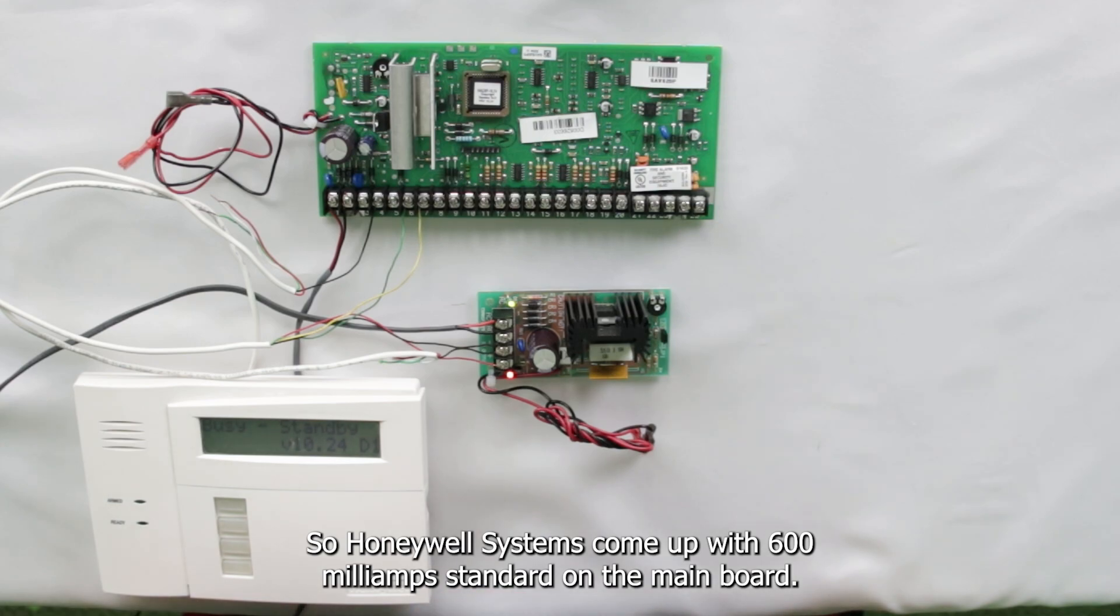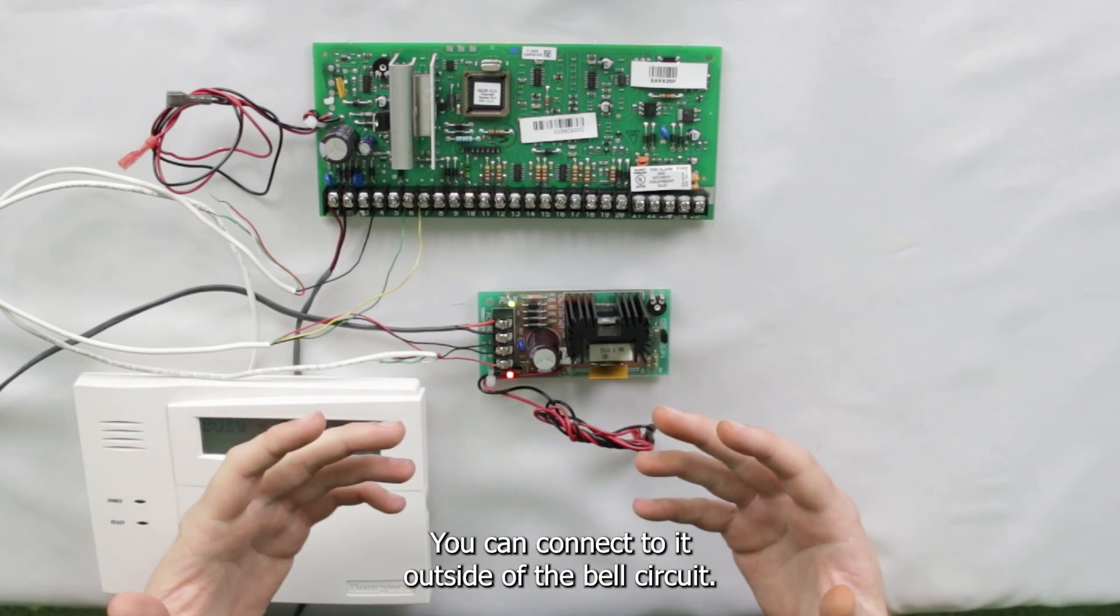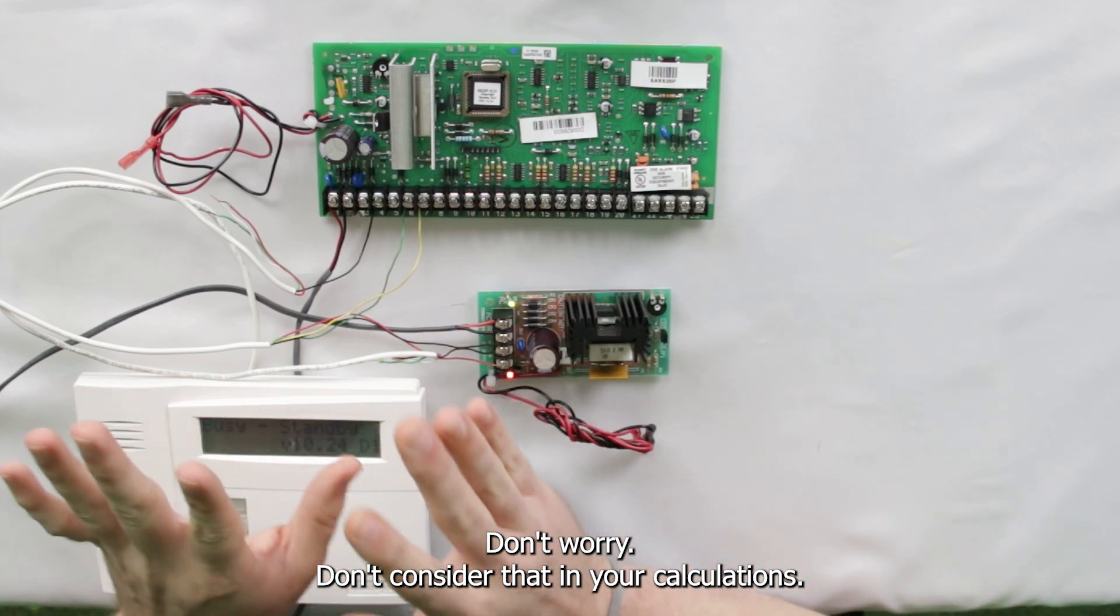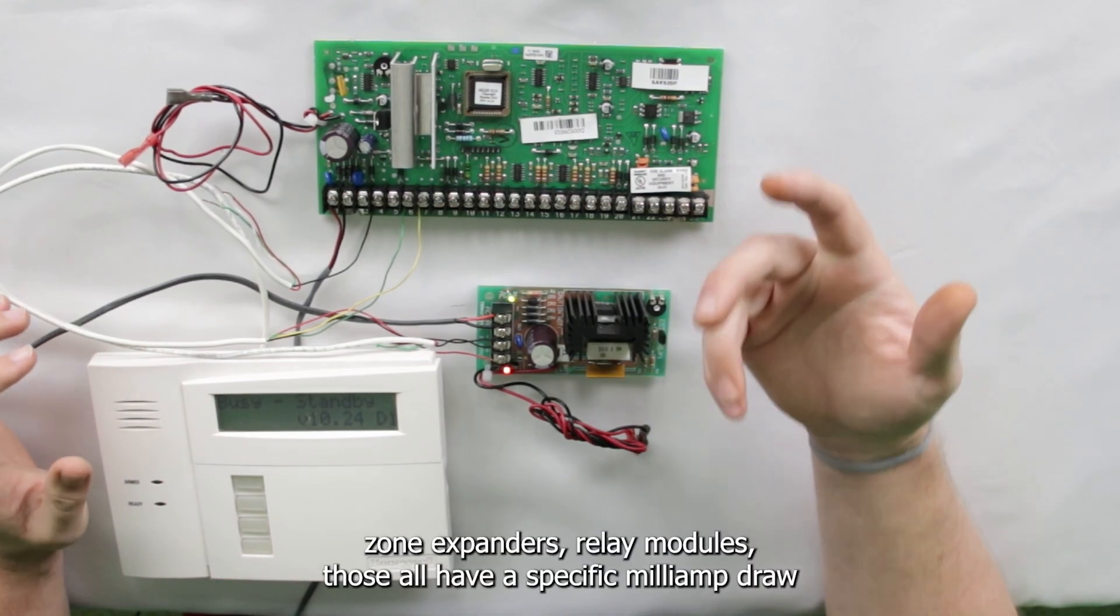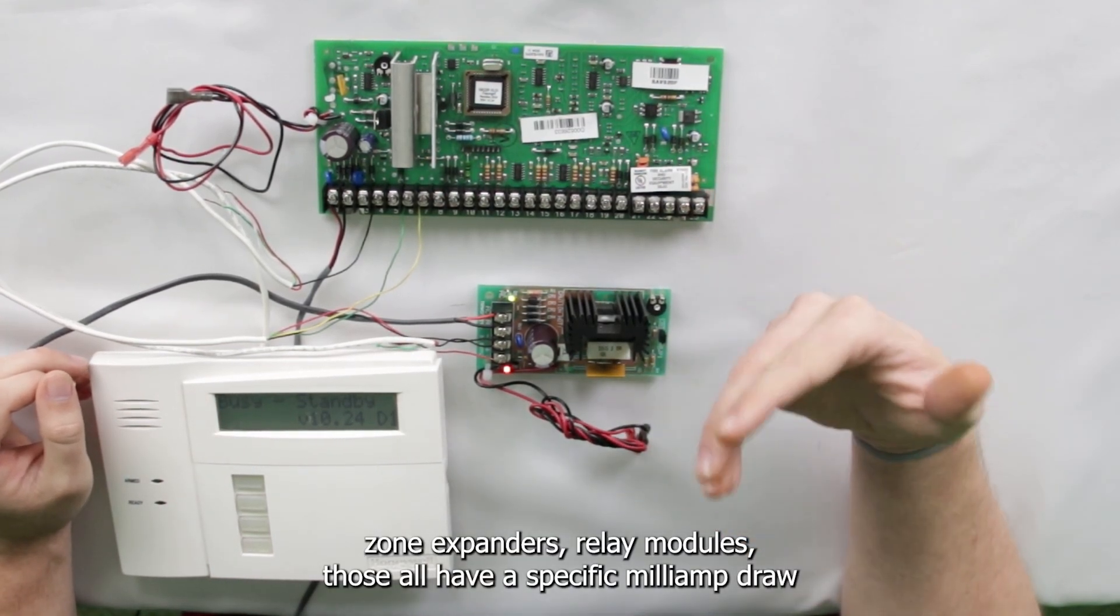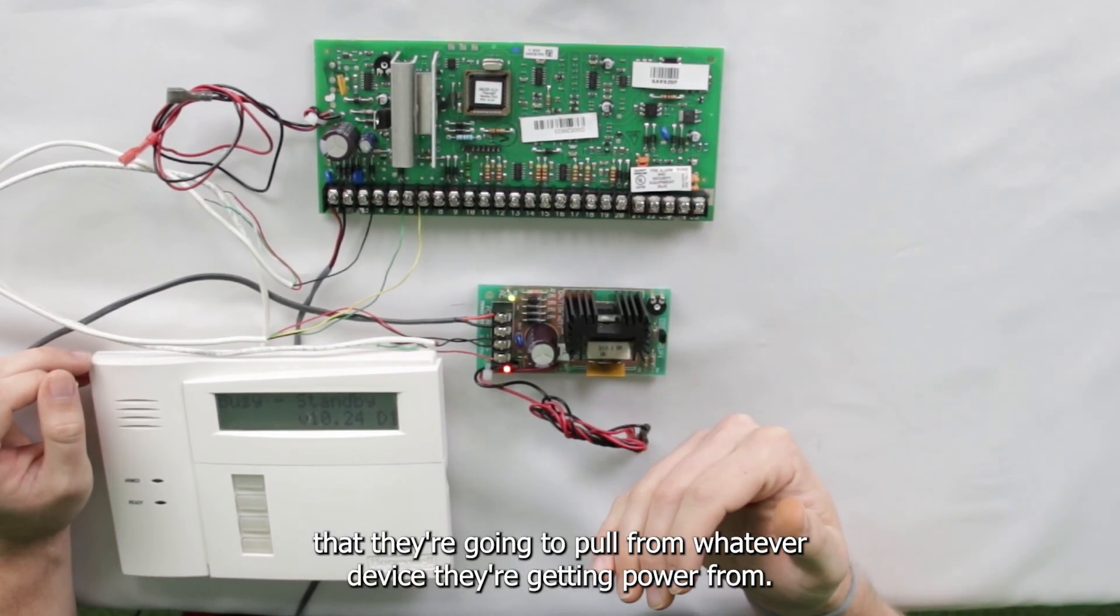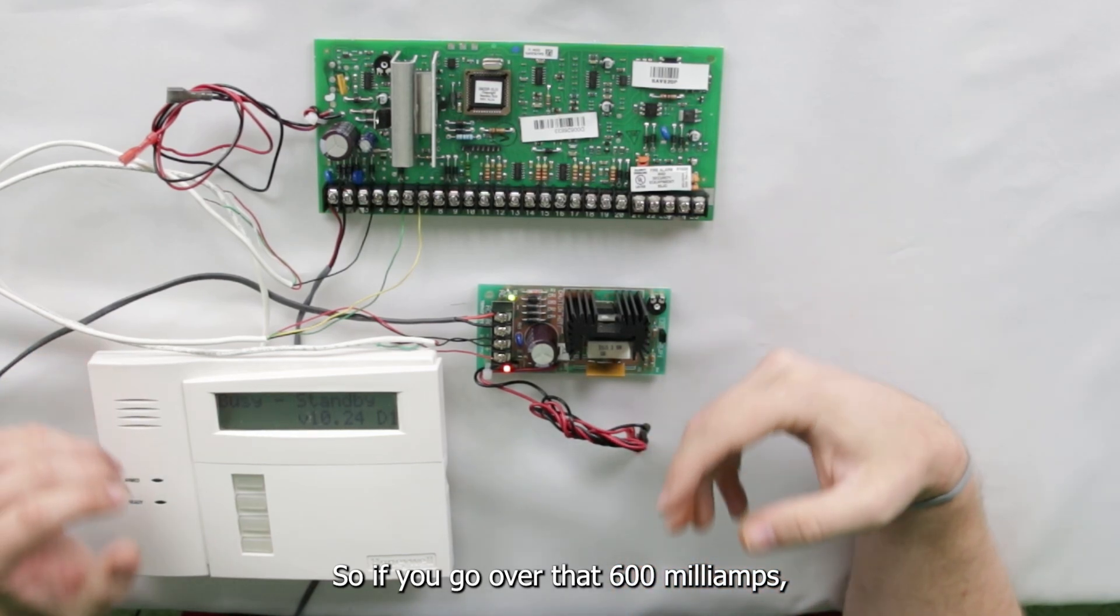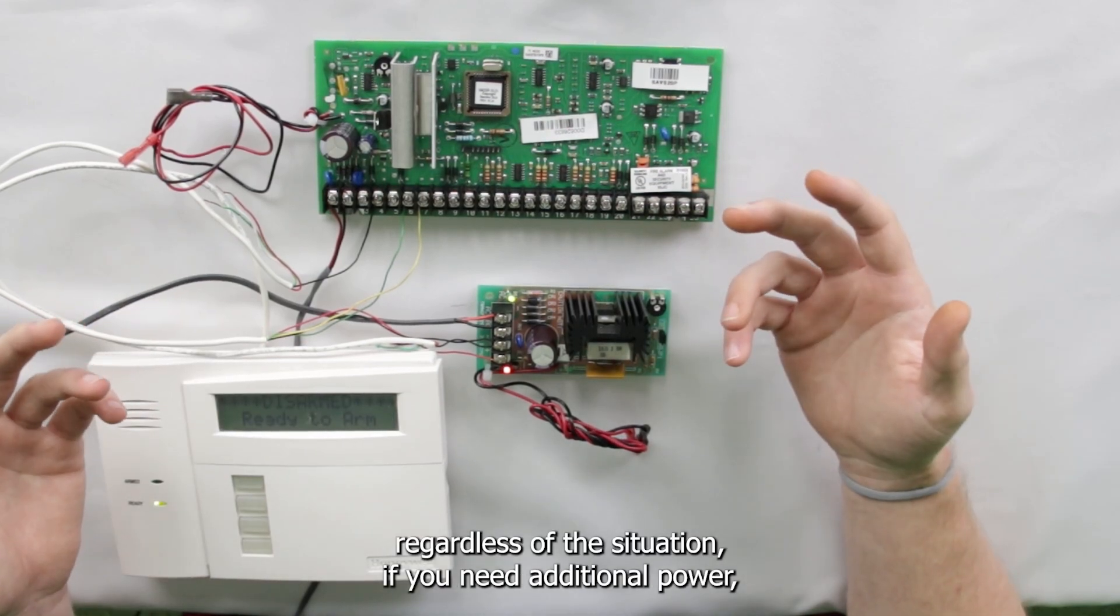So Honeywell systems come up with 600 milliamps standard on the main board. That's how much they can supply to everything you can connect to it outside of the bell circuit. That's always separate, don't consider that in your calculations. But whenever you're picking out modules such as keypads, zone expanders, relay modules, those all have a specific milliamp draw that they're going to pull from whatever device they're getting power from. So if you go over that 600 milliamps, basically it's not going to be able to handle all that, so certain devices will shut down.